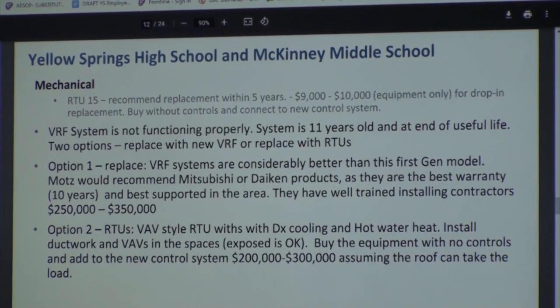All right, what else? VRF. So the VRF system, as far as I can tell, it's not functioning, or not functioning very well. There are some very good VRF systems out there, and if you want to stay with VRF, I'd highly recommend Mitsubishi or Daikin. Yes, they're expensive, but better today than 10 years ago. You've got a generation one or one and a half VRF system. You guys must have been one of the first users. VRF stands for variable refrigerant flow, that's the LG, those two white big condensing units out on the lawn.